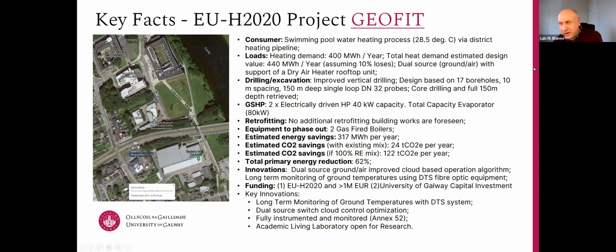We have an initial layout with 18 boreholes, with an initial calculation for a DN32 pipe, 150 meters deep, single loop. Note that this project is only for heating, so we are not balancing any loads through the seasons. We also had a core retrieved by Geological Survey Ireland of the whole 150 meter profile.